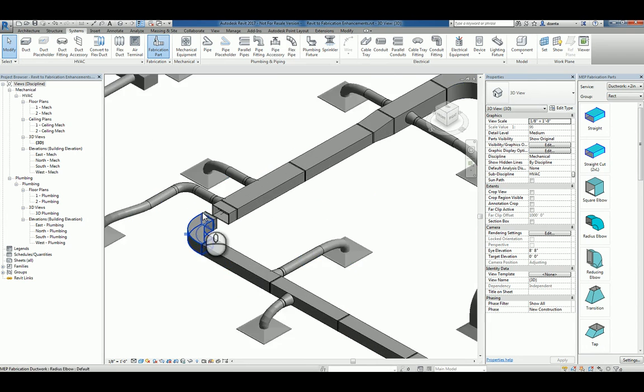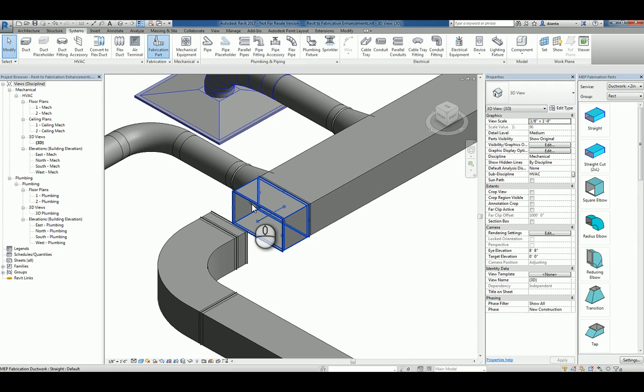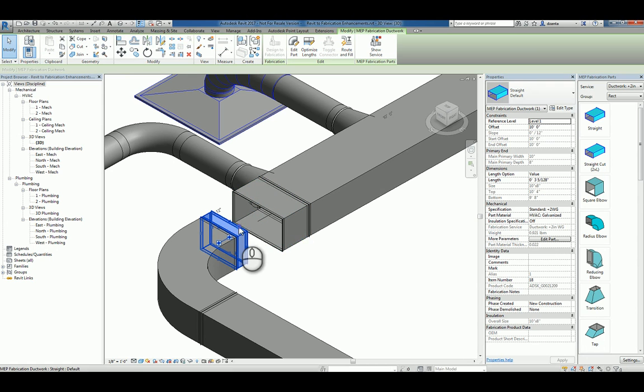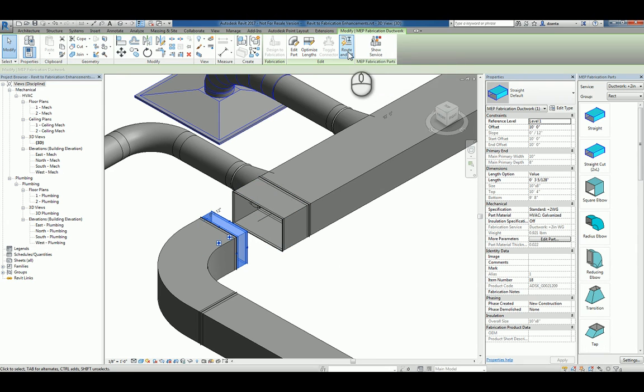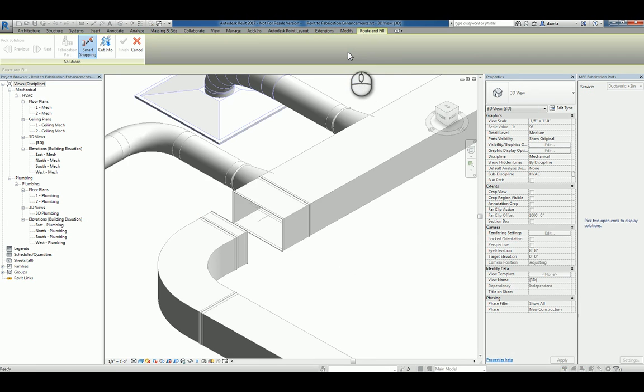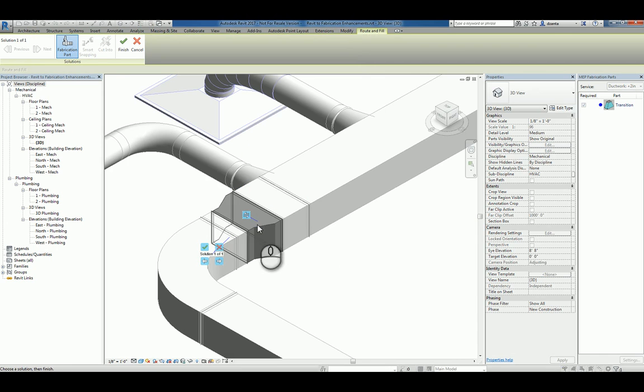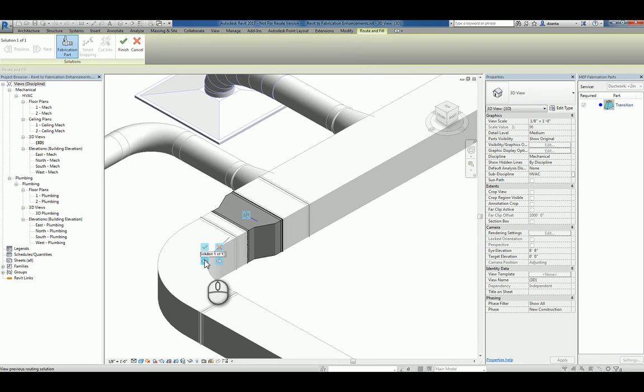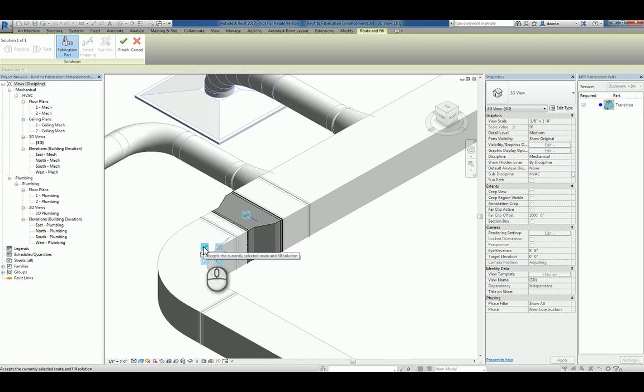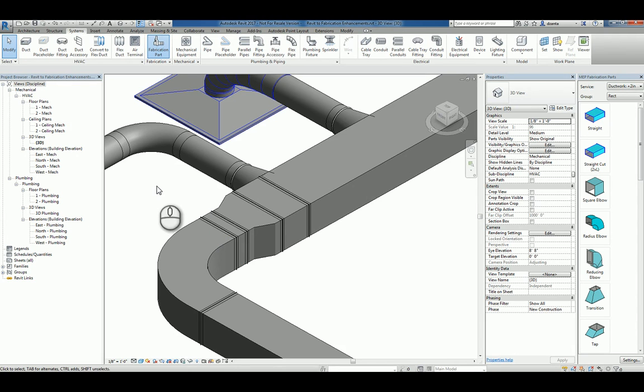And then you'll notice as well that we've got a design situation here that we need to correct. I can select the object, and if I need to, I can actually use a new feature called route and fill. What this allows me to do is tell it to connect to another endpoint node of another MEP fabrication part, and it will figure out what part to put in. I have multiple solutions available, and if I do, I can use the arrows to jump from one solution to another. I can click the green check mark to accept that piece, and it will finish it. Or I can click the green check mark in the contextual ribbon.